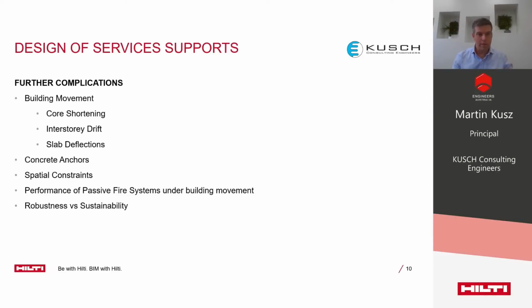Problems can also arise with stiff mechanical pipework in a plant room, where you might have a large chiller and a very large 350mm diameter pipe that connects rigidly to it on one floor and is supported and rigidly connected to the floor overhead. Interstory drift is going to create fairly significant forces in that whole system. Are they being considered? It's quite unlikely in many cases.